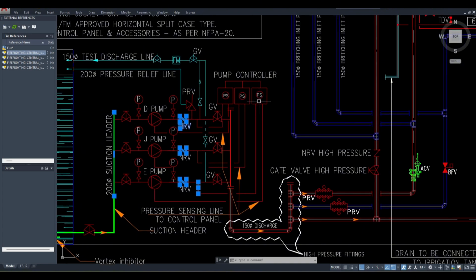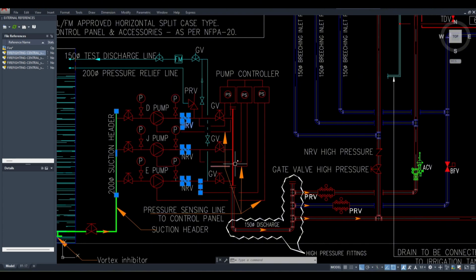Okay. So the control panel is equipment where mechanical and electrical connections are both there inside one box, one panel. And from there it works electromagnetically, like both. It's a combination of mechanical and electrical systems. So you can say an electromechanical system. So basically once this line is delivering the water, the pressure in this line after the NRV is the same pressure in this line, and this pressure is giving the signal to the sensor here. The sensor is activating or deactivating the electrical switch, okay, whether this pump should run or not run. Okay, so that's how it works. So this is the pressure sensing line.